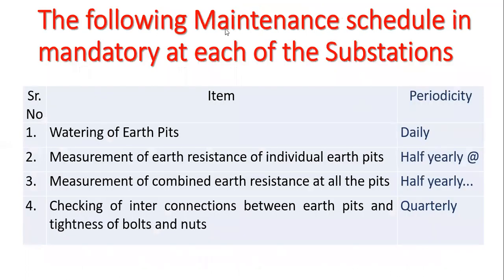Okay, next, the following maintenance schedule is mandatory at each substation. That means in each substation having any voltage, 11 by 0.44 kV, 33 by 11 kV, 132 kV substation. So these are the following maintenance schedules for the earthing that should be followed. So first of all, watering the earth pit. That means you have to water the earth pit daily, which is your periodicity, which is nothing but daily. That means daily you have to supply water to the earth pit. Then measurement of earth resistance of individual earth pit, that you have to perform twice in a year. That means half yearly you have to measure the value of the earth resistance for each individual earth pit.